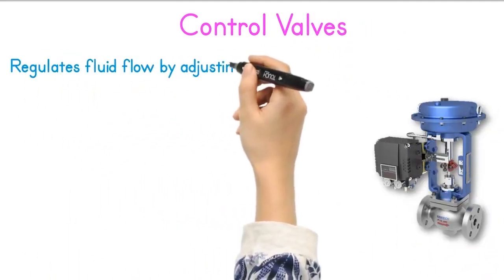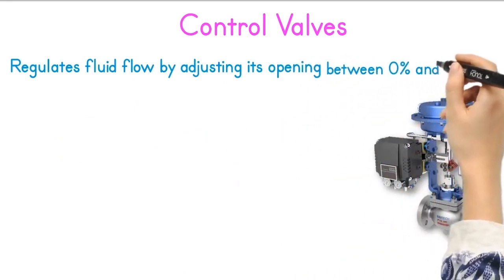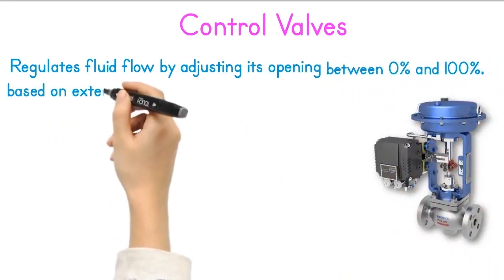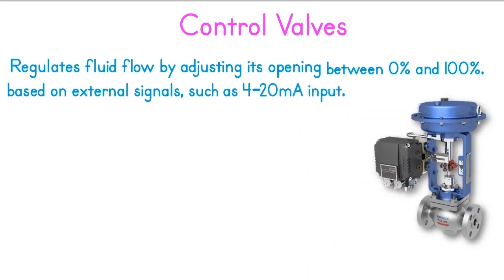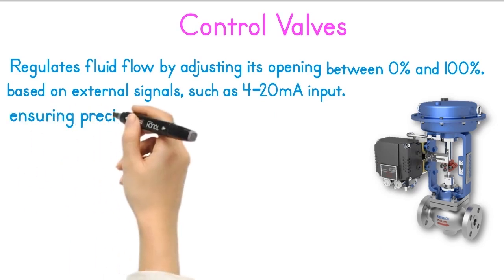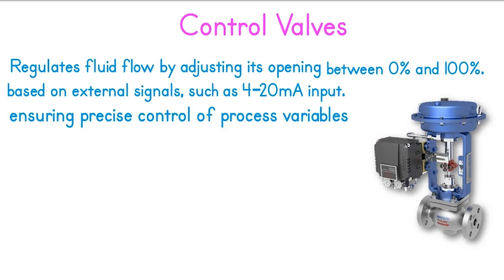Control valves. A control valve regulates fluid flow by adjusting its opening between 0% and 100% based on external signals, such as a 4 to 20 milliamp input. This allows it to adapt dynamically to changing conditions, ensuring precise control of process variables like flow, pressure, temperature, and level.